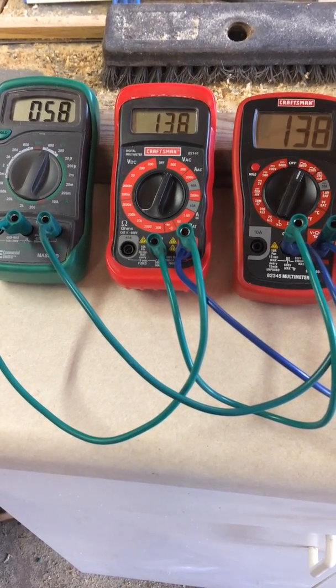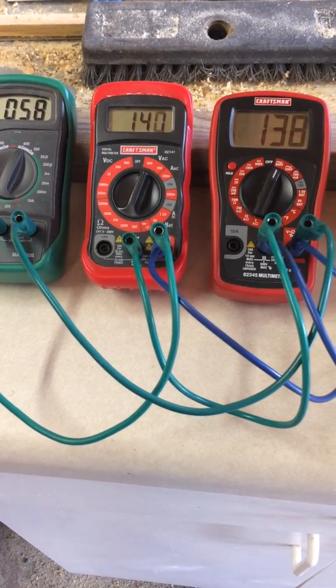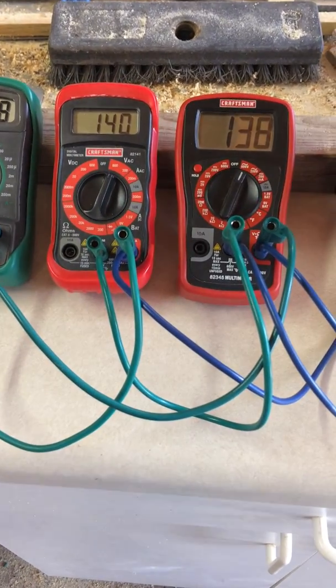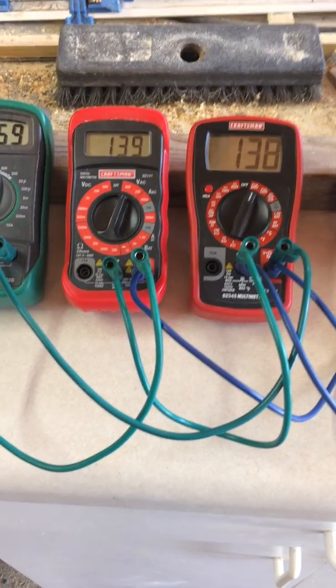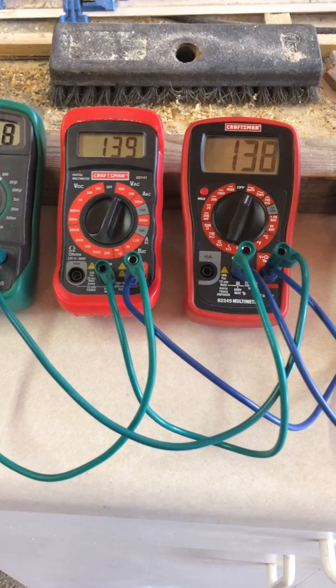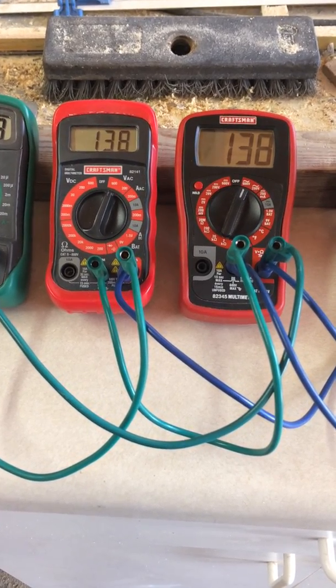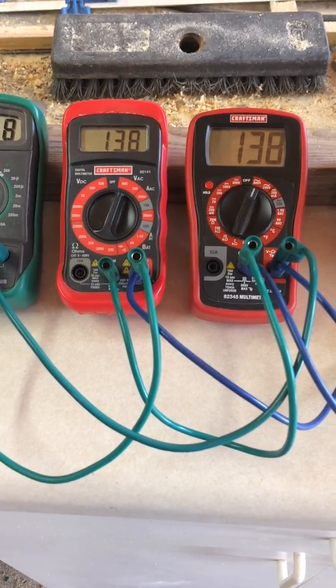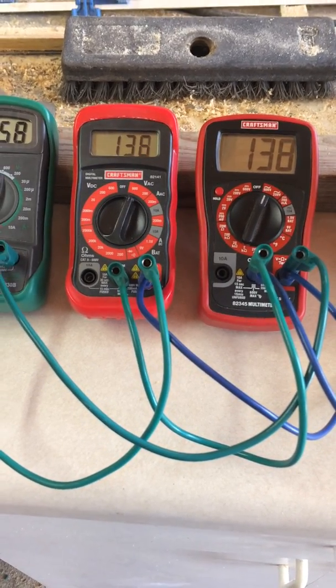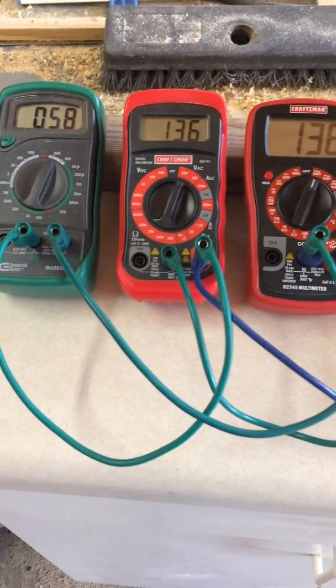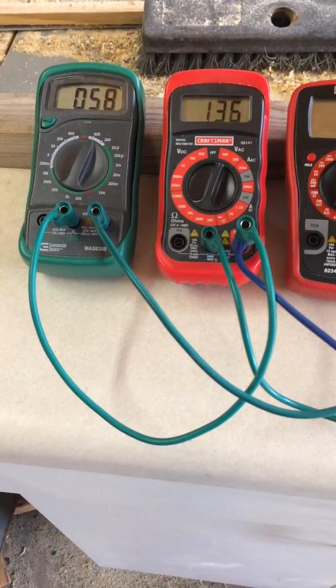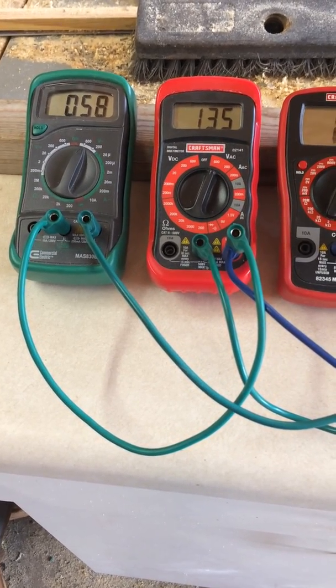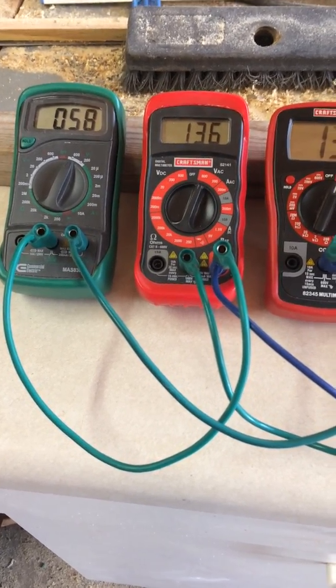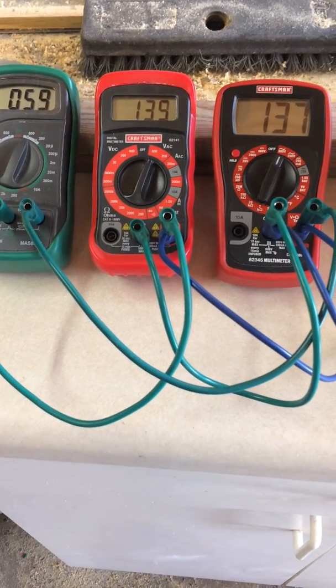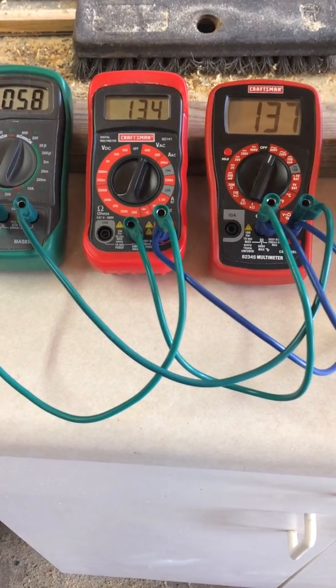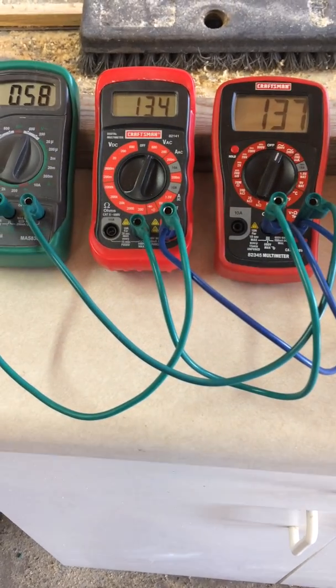As I start to increase the voltage just a little bit, all of a sudden you hear the fan increase in speed because the voltage went up to 140, but the voltage across the capacitor went up to 139 or 140 as well. So both of these are operating over the rated voltage of the fan, but notice that the supply voltage is still sitting at 58 volts. I didn't increase the voltage that much, but all of a sudden we got into a situation where there's energy being transferred back and forth between the capacitor and the vent fan.